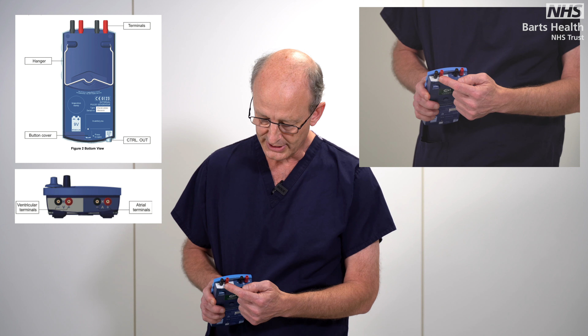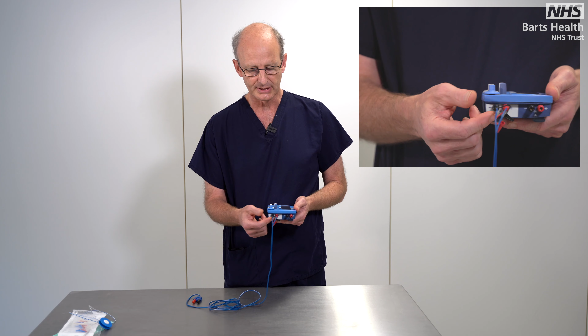So that's very straightforward. It's a matter of unscrewing the terminals for whichever lead that you want to connect, and then placing the leads in, and then screwing up the sockets like that, nice and tight so they don't fall out. Remember to get them the right way round. In other words, the ventricular wires must be in the white side and the atrial leads in the blue side. If you get them the wrong way round, obviously the pacing is going to work in a reverse direction. It doesn't matter whether you put the black and the red into the wrong sockets. Okay, it will work either way round.